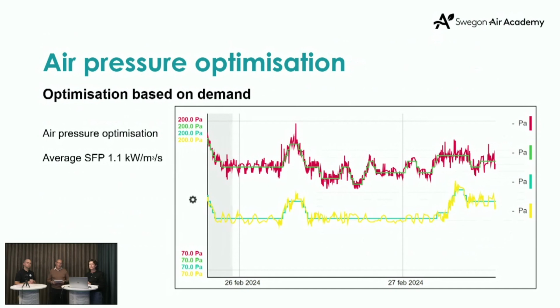If you look at the red curve, it's the extract air duct, and the yellow curve is the supply air. What you can clearly see is that when people come to work in the morning, the pressure needs to go up because the ventilation rates need to go up. But during the day it varies - people are coming and going, but we always keep as low pressure as possible, so we save fan energy, but also CO2 emissions.